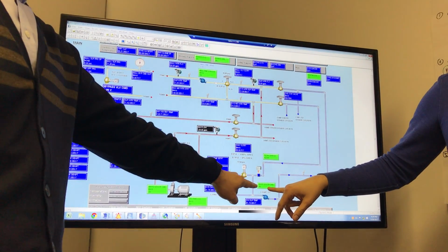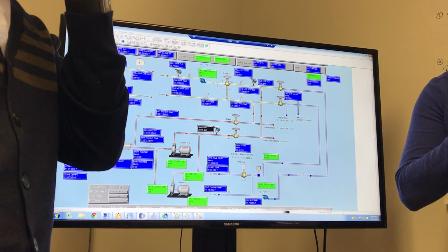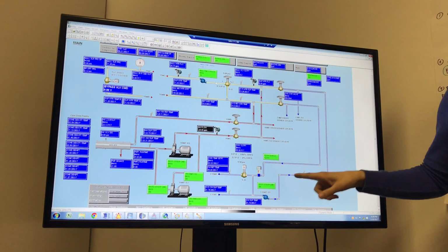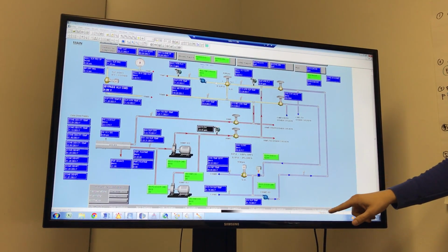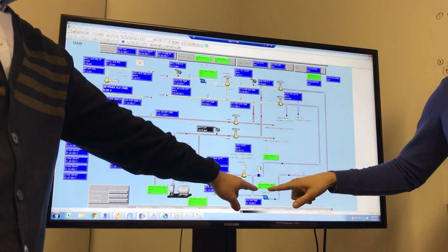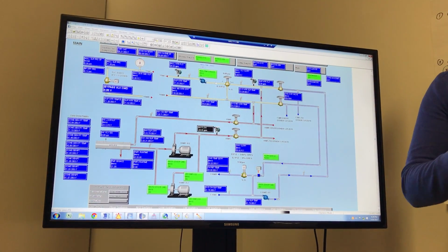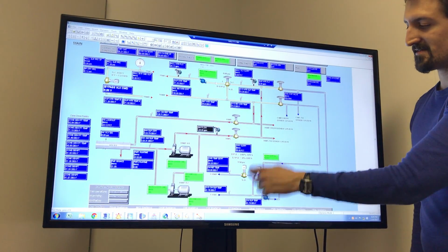I cannot tell from here. This cooling loop is not just for us; it's for the whole building. Should be on all the time. It's not controlled by us. This is really important for the entire building, right? It was not like this before, but they tied to our feed somewhere here. They added one feed, which was not there before. So not a good idea to turn this off. Maybe other rooms require it. Before, because it was only us, this one would turn off, this one would turn off. So now this is on all the time.